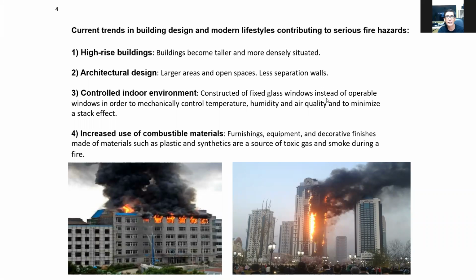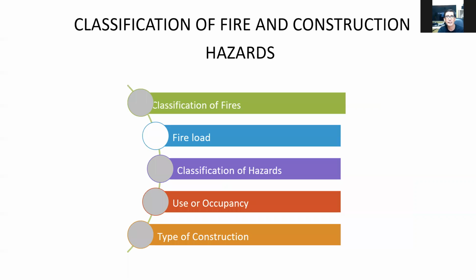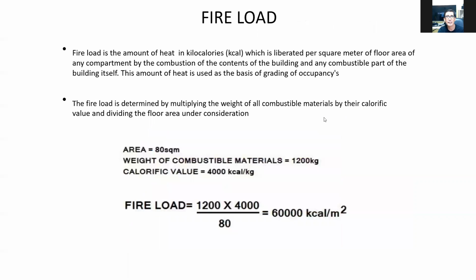So classification of fire and construction hazard. Number one is we have to consider the classification of the fire load, the classification of hazard, the use or occupancy, and the type of construction. So these are the classification of fire and construction hazard. So the fire load is the amount of heat in kilocalories which is liberated per square meter on a floor area of any compartment by a combustion of the content of a building and any combustible part of the building itself. This amount of heat is used as a basis of grading or occupancy.